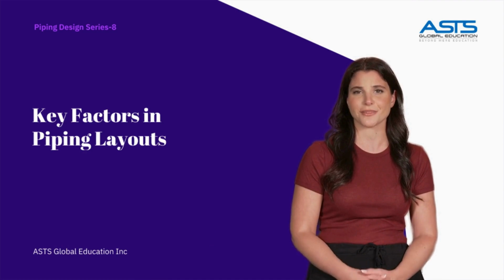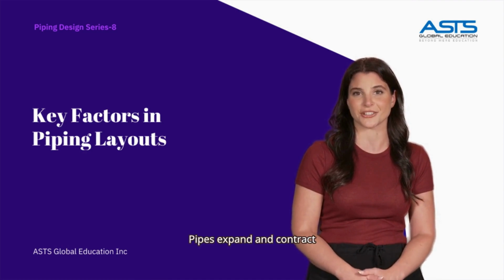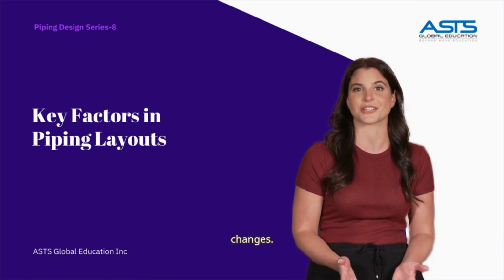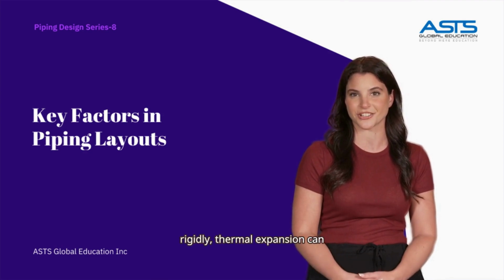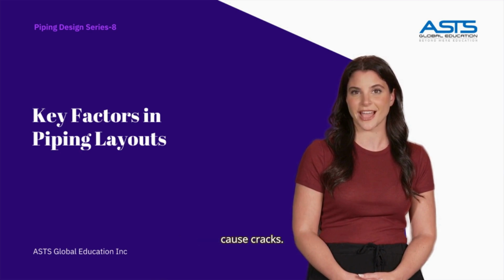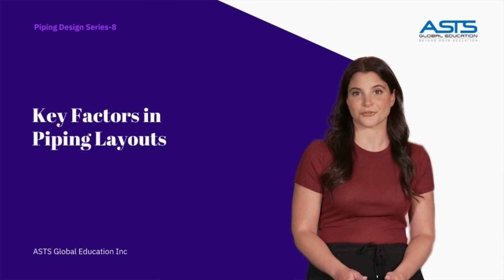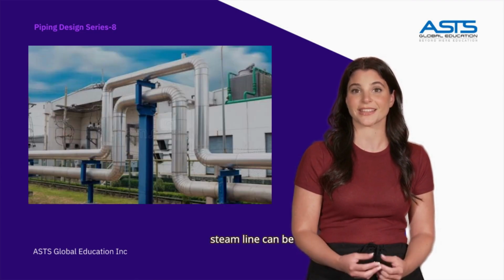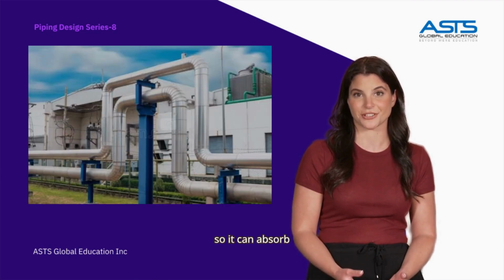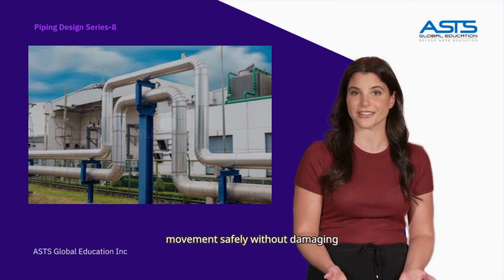Flexibility is another key point. Pipes expand and contract when exposed to temperature changes. If we connect them rigidly, thermal expansion can create stress and even cause cracks. To avoid this, we use expansion loops or flexible offsets. For example, a long steam line can be arranged in a U-shape so it can absorb movement safely without damaging the connections.